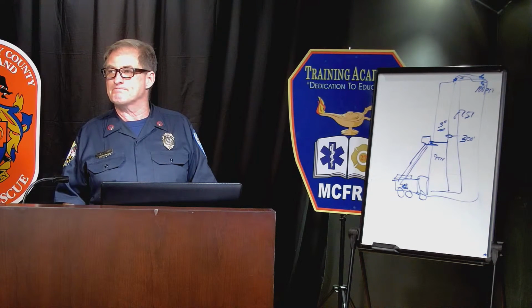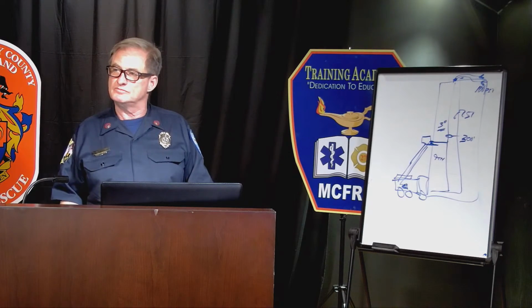Can I ask you a question from an engine company standpoint? Yes. If that break would have been not on that horizontal from the pump to the riser, but on the riser itself, could we quickly talk about a workaround with that? I think your workaround, if the break was in the riser, would be to, again, go to your riser isolation valve, shut it off, put that riser out of service, and go and use your other risers. Okay. I think that's your answer there.